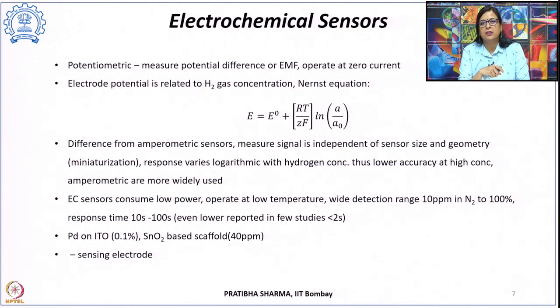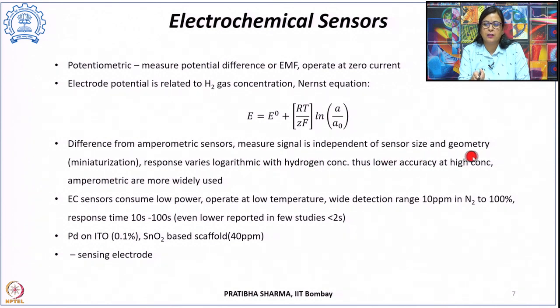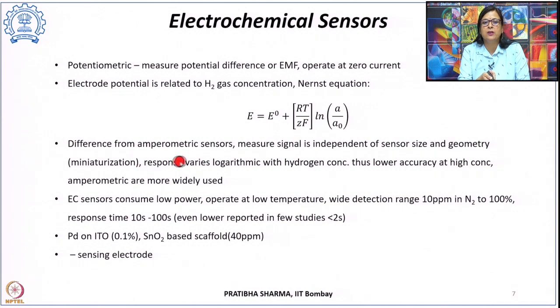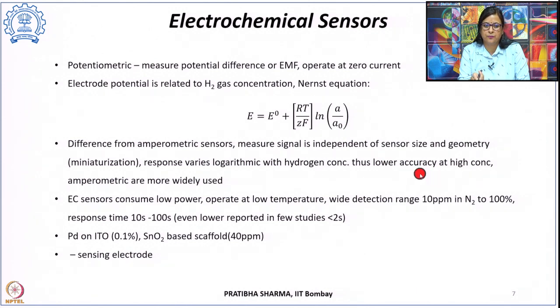A key difference between amperometric and potentiometric sensors is that the potentiometric signal is independent of sensor size and geometry, enabling miniaturization. However, the logarithmic relationship between electrode potential and hydrogen concentration means lower accuracy at higher concentrations. Amperometric sensors are therefore more widely used than potentiometric types.